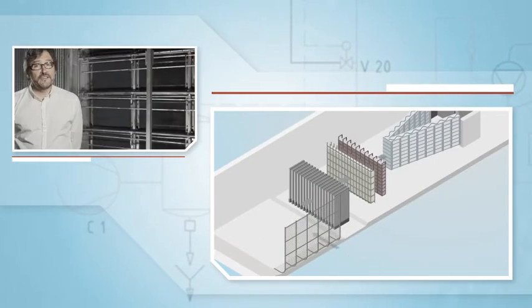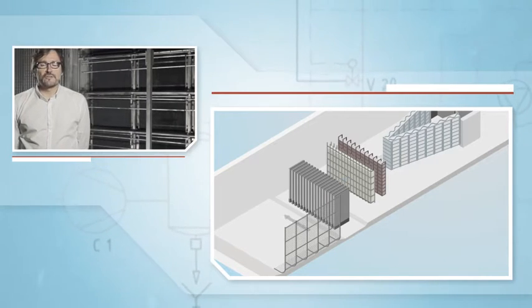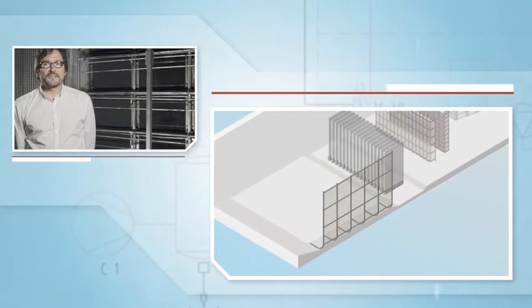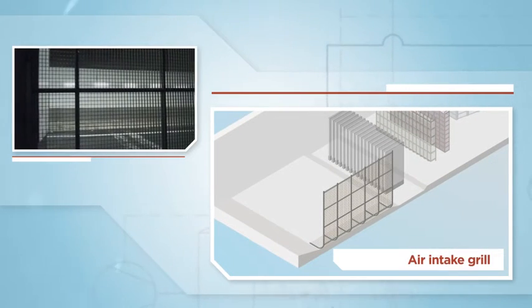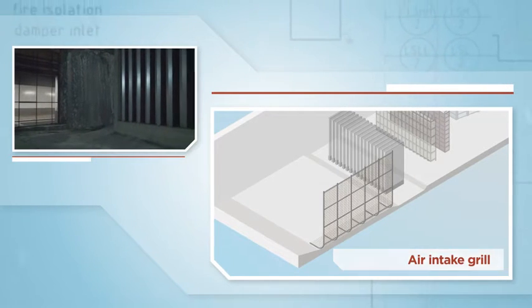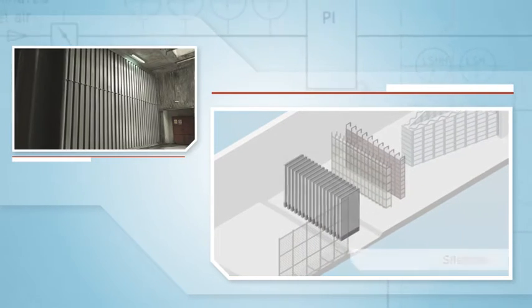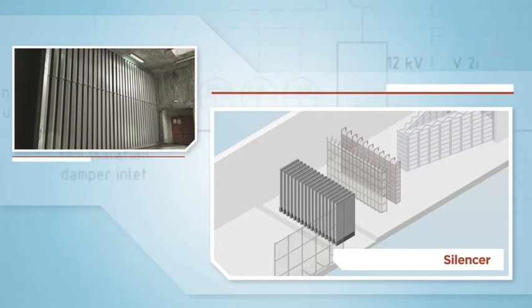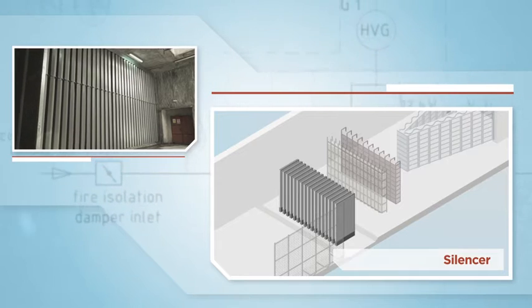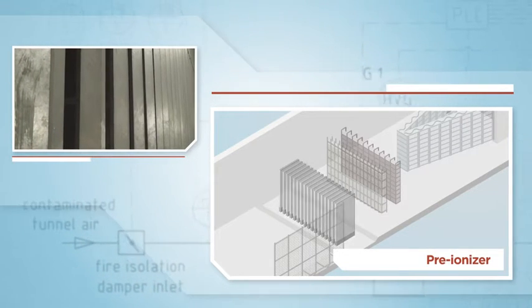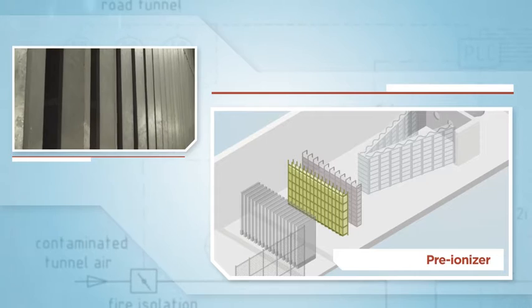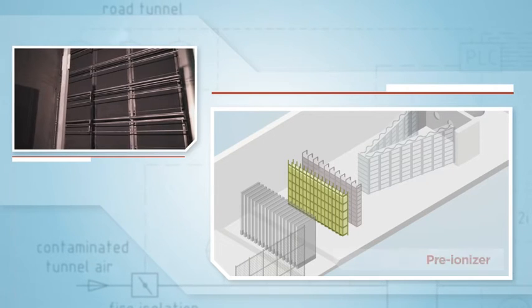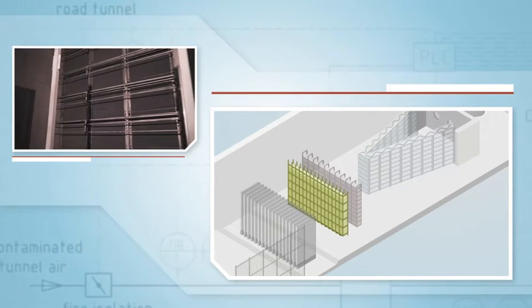Following the airflow, a standard installation comprises an air intake grill to retain larger objects like papers, plastics or leaves, followed by a silencing unit to reduce the noise. Then the air is conducted through the preionizer unit used to increase the efficiency of the electrostatic precipitator.